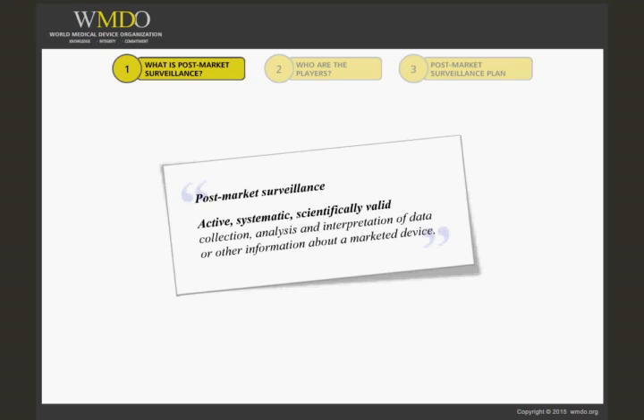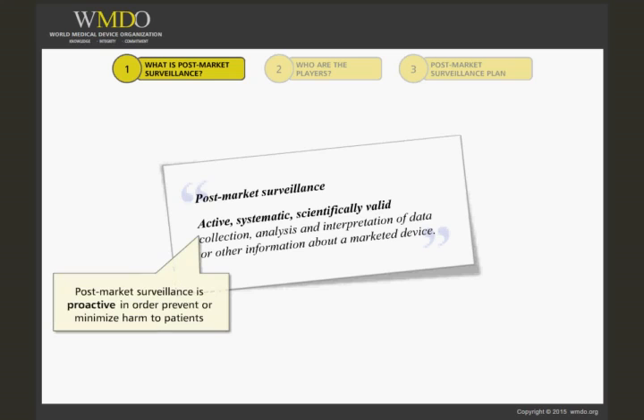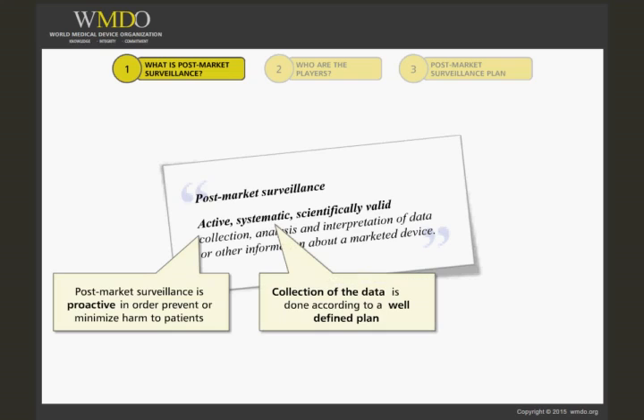There are several elements in this definition that require closer attention. 'Active' suggests that post-market surveillance should be proactive in order to collect sufficient data on a product, so that harm to patients can be prevented or detected early enough so that any harm can be limited.